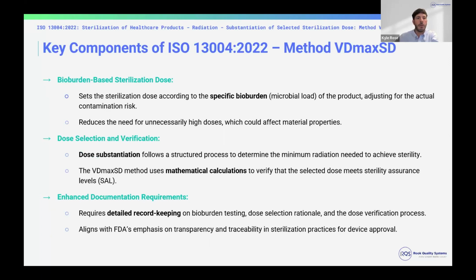Key components of the standard. So making sure you have a sterilization dose that's aligned with your product, your microbial load, and adjusting for the contamination risk, reducing the need for overly high doses, which could affect the material or packaging, using dose substantiation to determine the minimum radiation needed to achieve sterility, and then aligning with the calculations and formulas provided in the standard to identify this VD max SD to meet your sterility assurance level, or SAL. It also provides additional documentation requirements to make sure that you are keeping up with the records for this testing, making sure you have the correct dose, rationale, and this has been validated. You also need to verify with each sterilization batch that you're meeting the requirements of your dosing, right?